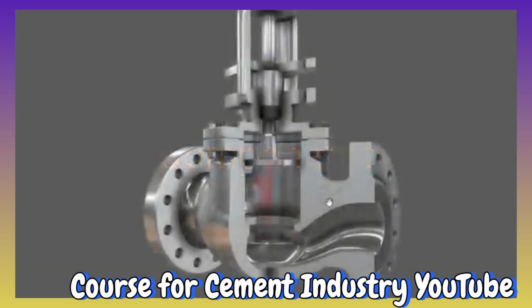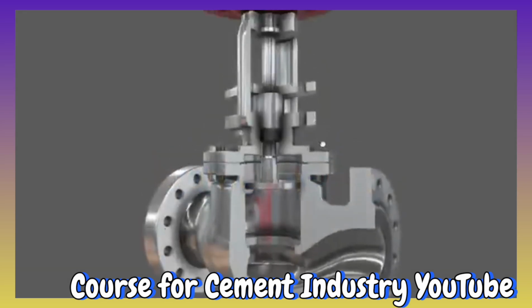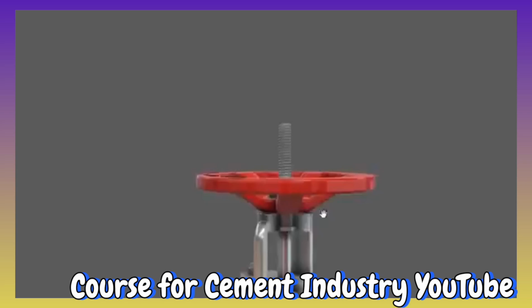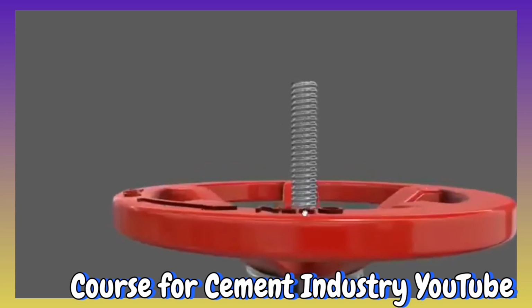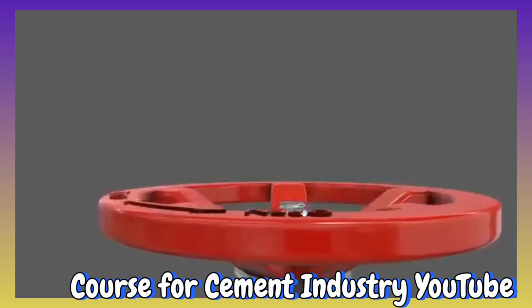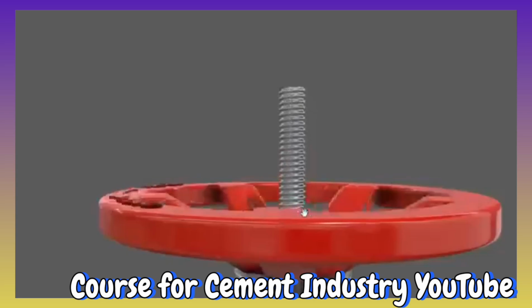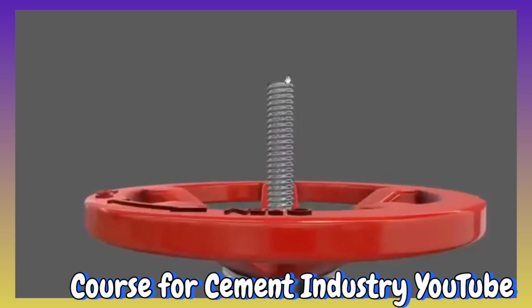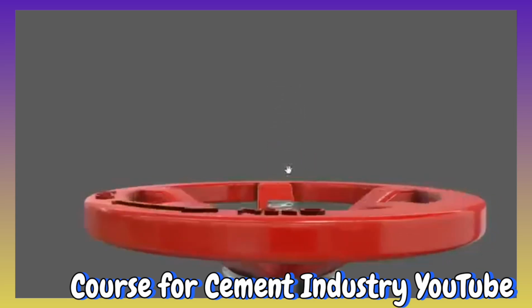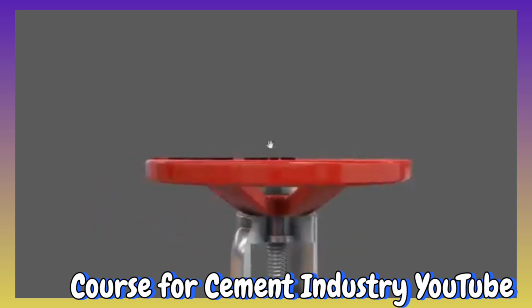Let's just have a look at the top of the valve and talk about some of the components. We can see that it's got what they refer to as a rising stem. The rising stem indicates the valve's position. Now the valve is open, we can see the stem is popped out of the top, and now the valve is closed. We can see also that the valve is mechanically actuated because we're using a hand wheel.